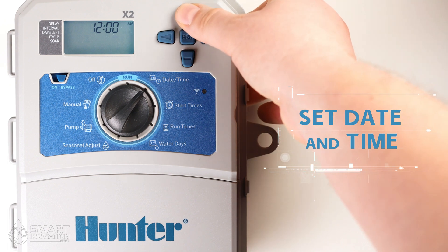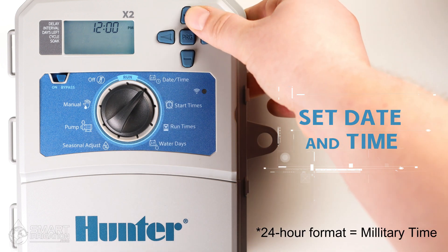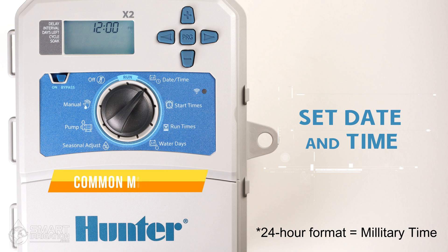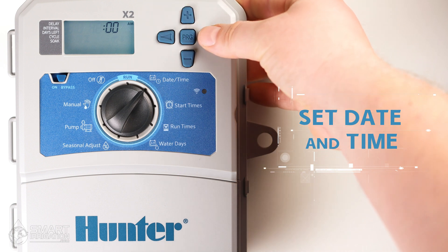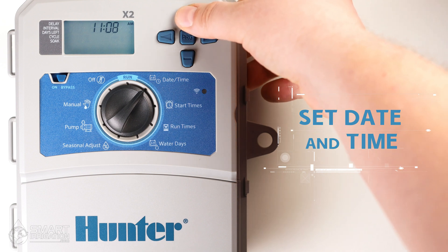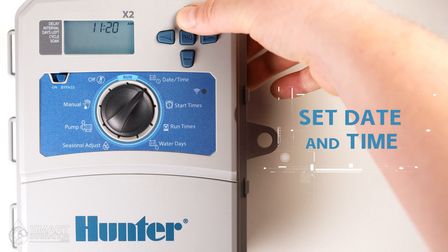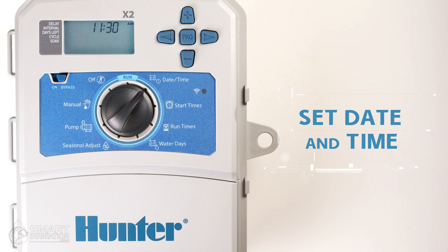Use the right arrow to go to the next item: the time format. You can select either 24-hour or AM/PM. One of the most common mistakes that we see is that AM and PM on the clock are switched, so pay extra attention to this setting or use the 24-hour setting if you prefer. The next setting is the hour, then set the time. If you hold down the button it'll scroll through the items faster. Another important tip is to make sure you change your controller's time with daylight savings time.